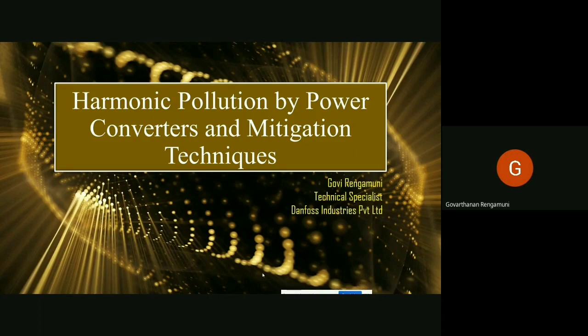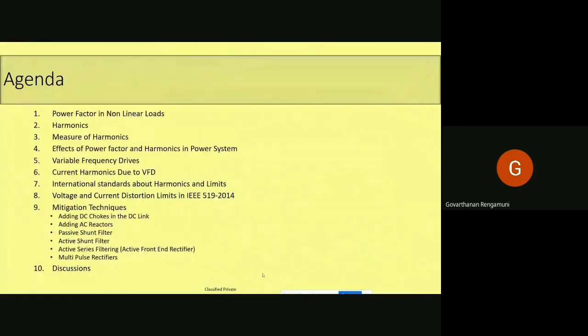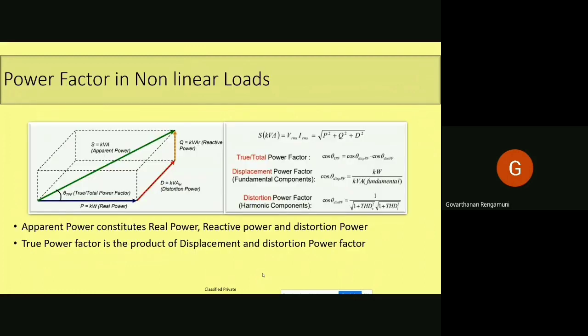So from this preface, we can start this session. The session agenda has been sequenced like this. The power factor in nonlinear loads, starting from that. Then what is harmonics and measure of harmonics, the effects of power factor and harmonics in power systems, variable frequency drive as a power converter, current harmonics due to variable frequency drives, international harmonics standard limits, and voltage and current harmonic limits prescribed in IEEE 519. Then different mitigation techniques. Finally, some discussions. This is going to be the agenda for today. Now let us start with power factor.